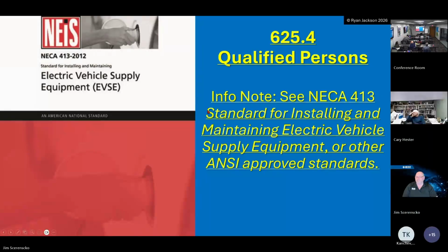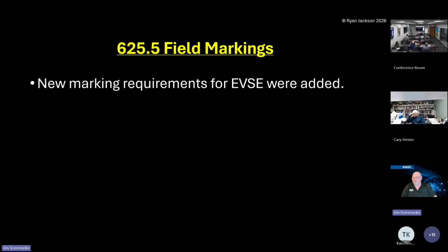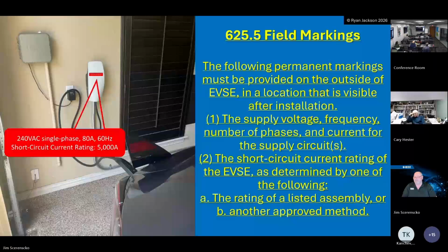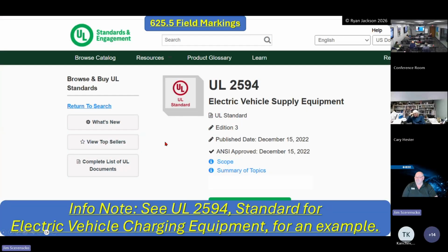Qualified persons, like I said, there is a definition in an informational note in NECA 413 for what a qualified person is. 625 also has new marking requirements for EVSE. The following permanent markings must be provided on the outside of the EVSE in a location that is visible after installation: the supply voltage, frequency, number of phases, and current for the supply circuits, and the short circuit current rating of the EVSE as determined by one of the following: the rating of a listed assembly or another approved method. So what's the available fault current for the short circuit current rating? There have been a lot of problems with this electric vehicle equipment, because this would be the standard.